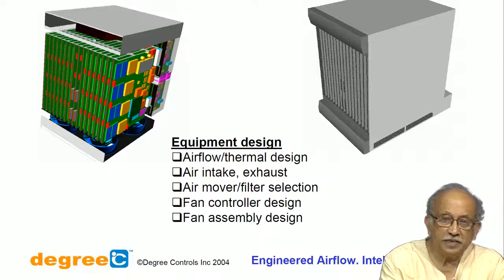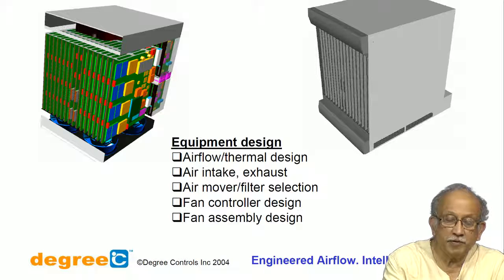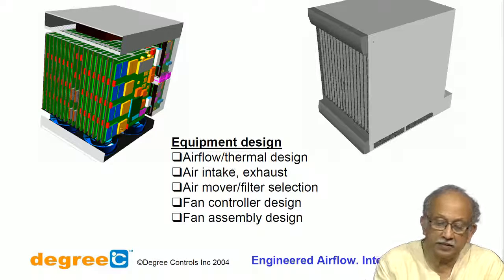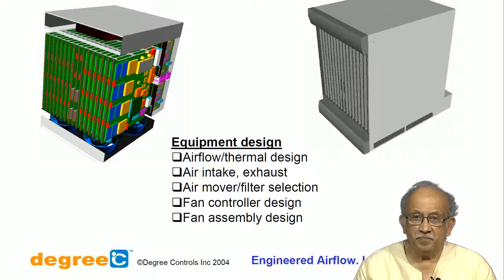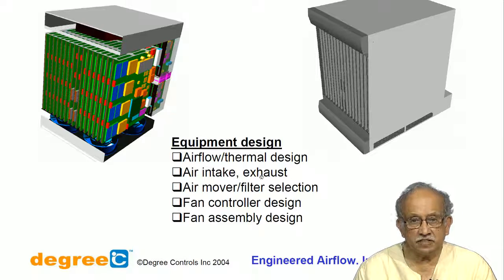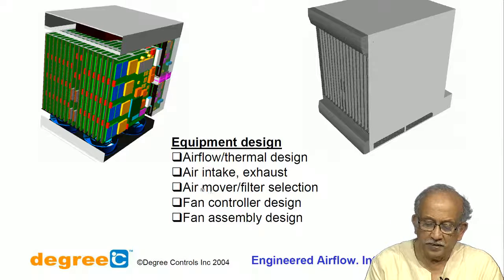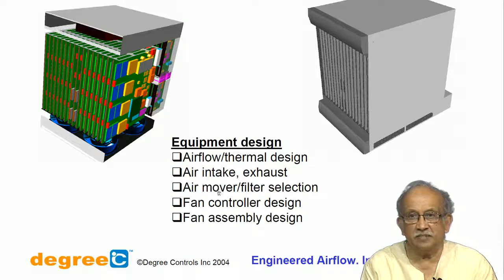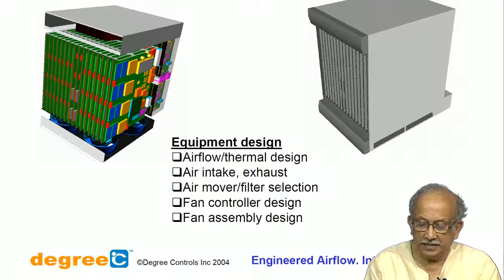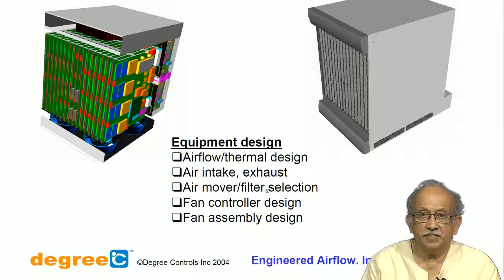You need to consider where to take the intake and where to exhaust. Exhausting directly on top looks nice, but you still have the problem of dripping water and things falling from above. If condensation occurs, a smooth channel is not easy to establish. You will invariably end up exhausting on the sides or at the back. Location of air intake and exhaust is critical. Then we come to the actual device that moves the air — loosely we call it a fan: axial, tube axial, or externally mounted fans with air filtering.